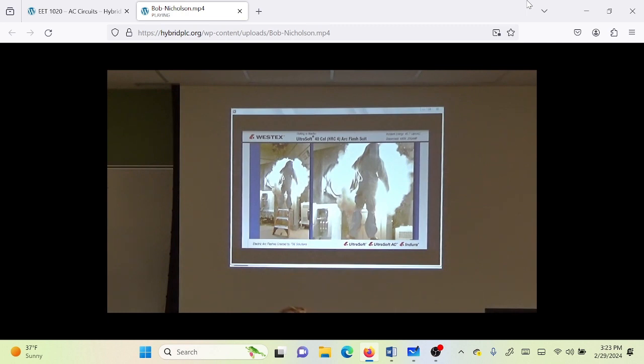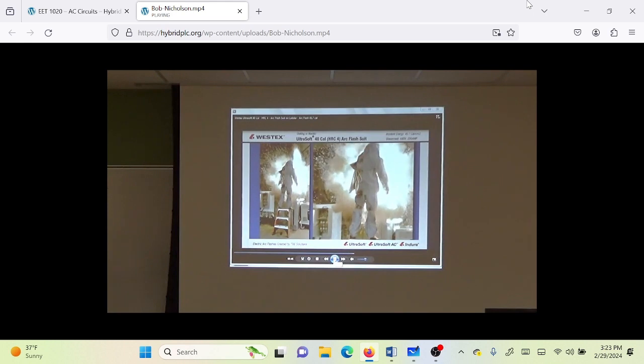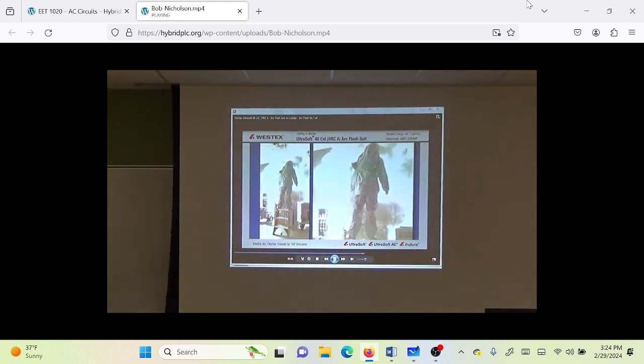So this is going to go on for a while until something turns it off. The previous clothing would not withstand this. This clothing is much thicker. This guy survives because he's got that suit on. There's a wall of molten metal going in all directions, and the arc eventually defeats the sides of the MCC as well, and we get the arc plasma out to the right and left of the mannequin.